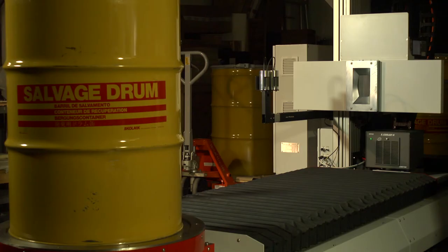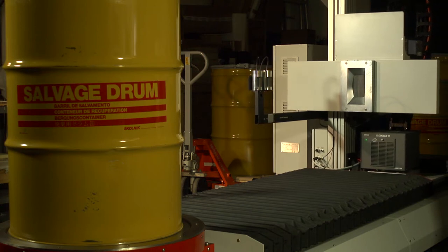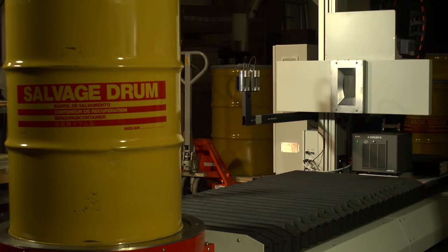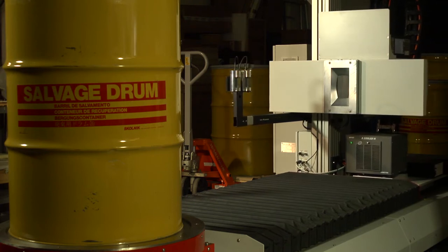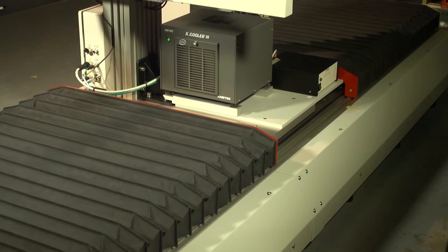The Antech Far Field Gamma Monitor is designed to measure radioactive waste in drums with a range of radioactivity content and waste density. The purpose of the measurement is to determine the inventory of radionuclides contained in the drum or object being measured.